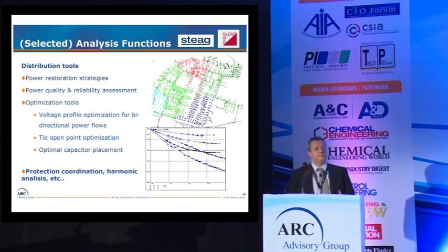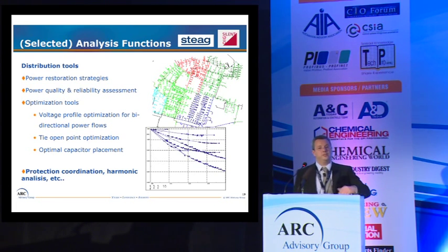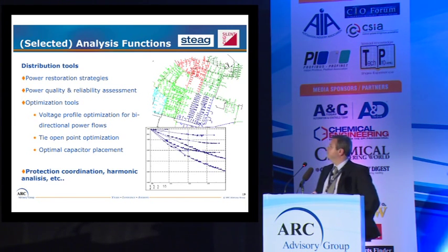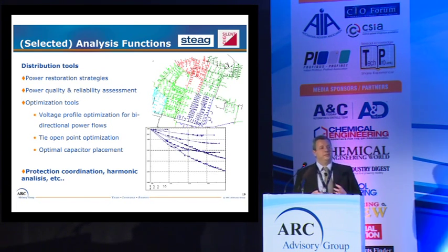Everything that is converter-based generation will normally inject harmonics into the system. We need to look at the total harmonic distortion in the different buses, and what is the reliability of the system. These are functions that are part of the simulator.